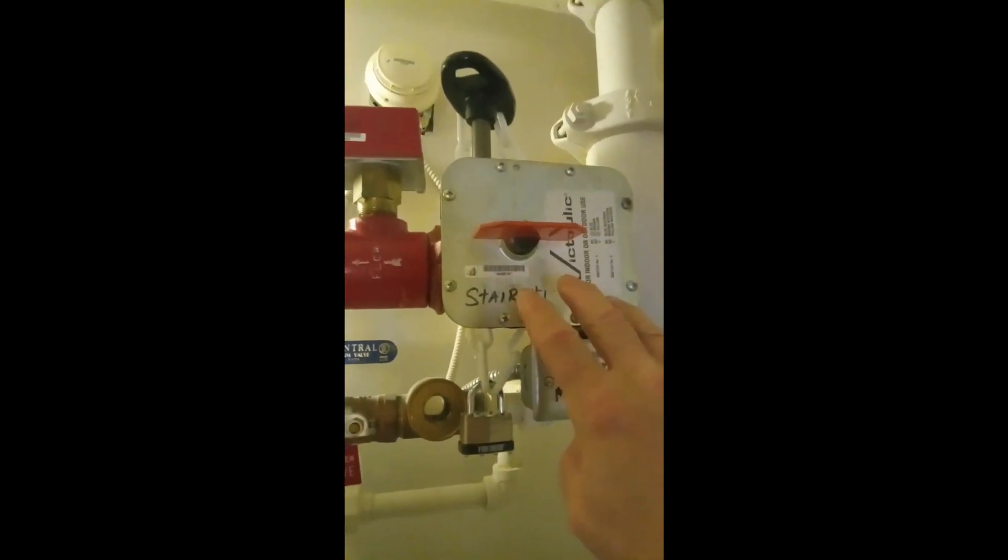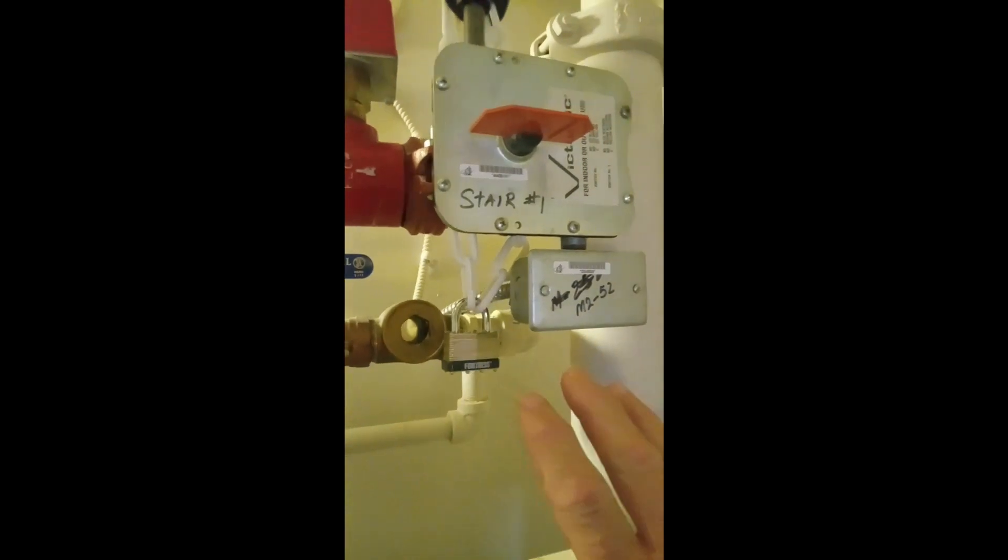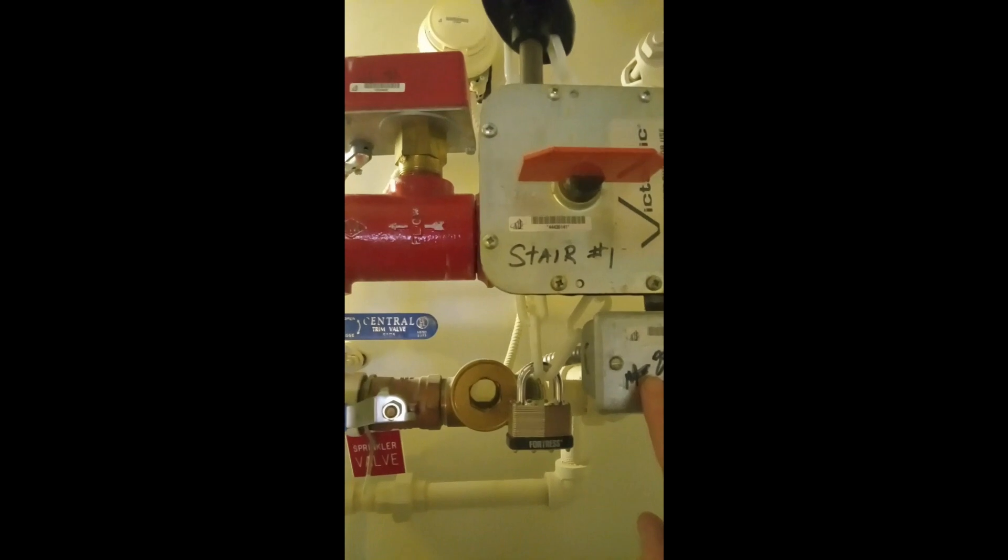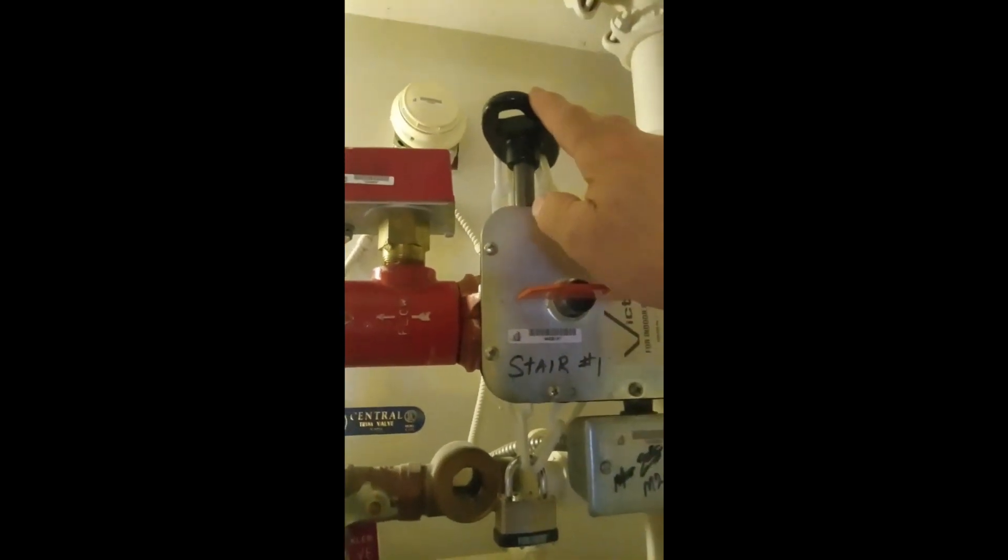This is the shutoff valve. The shutoff valve has a lock to prevent any unauthorized use. The shutoff valve is connected to what is called a tamper. When the shutoff valve handle is turned, it sends a signal to the fire alarm panel telling us that someone is turning off the water to the sprinkler system.